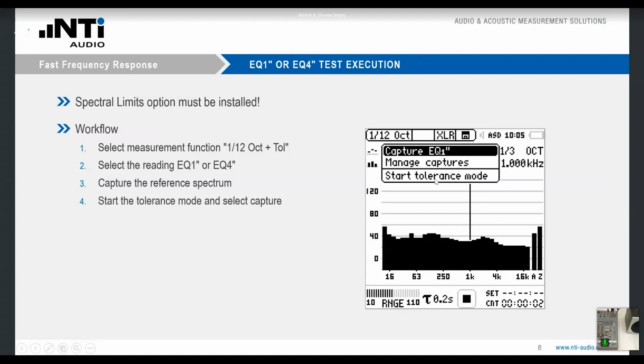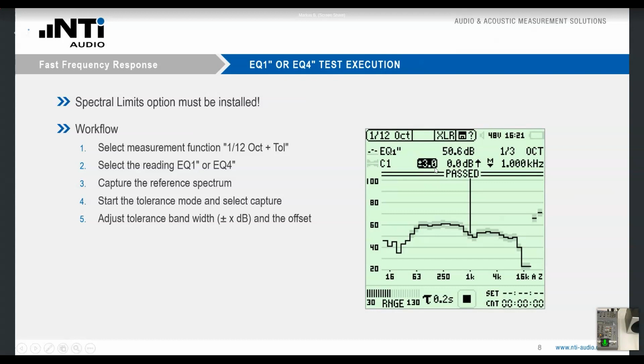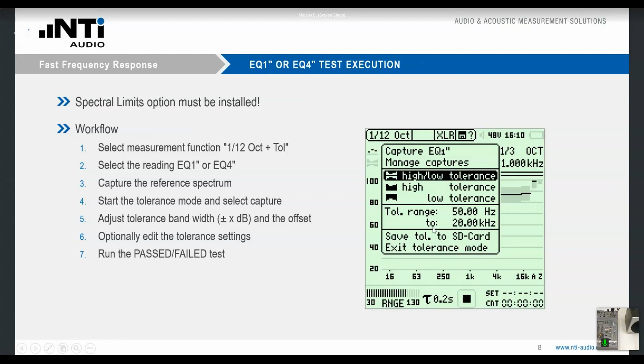Next, you would select here the start tolerance mode menu entry and select the previously saved capture from the memory, from the onboard memory. If necessary, you can adjust the width of the tolerance band, as you can see here. I also show that to you, and of course also the offset if necessary. You can, if necessary, adjust or edit the tolerance settings, the tolerance width. You could also say, do you want to have a plus-minus tolerance or just a plus or only a minus tolerance band? So this is up to you. And having done that, you're ready to execute and run the passed-failed test.